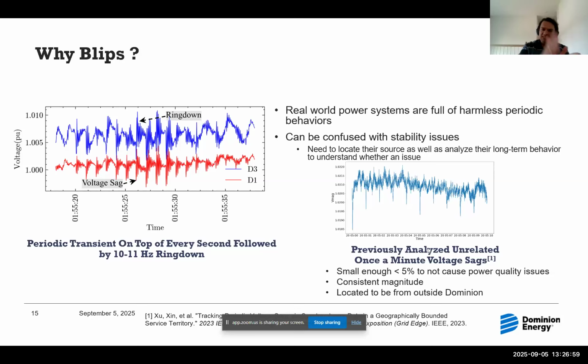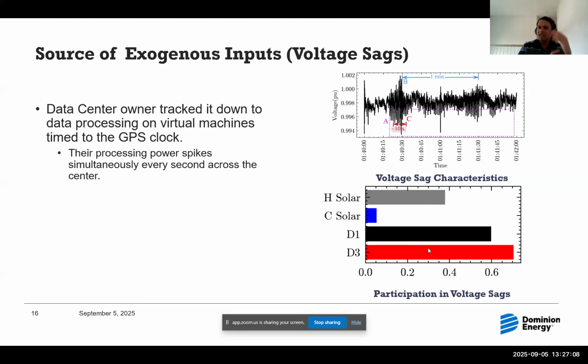So there is a periodic excitation on the system that excites some dynamics in this part of our setup. Where did these periodic excitations come from? Tracking the source, this particular one is the data center itself. The data center has the maximum participation in these periodic voltage sags. Essentially, the data center has some process happening precisely every second, which kicks the system and lets us see the impulse response from that point.